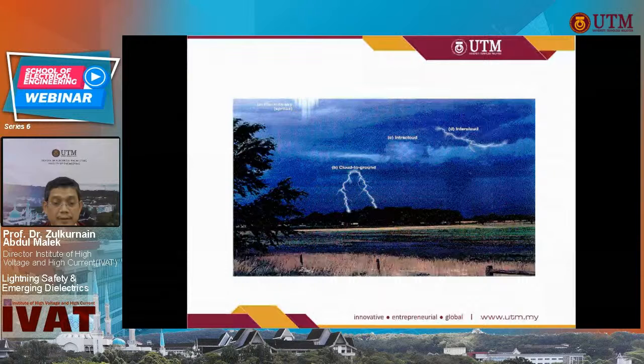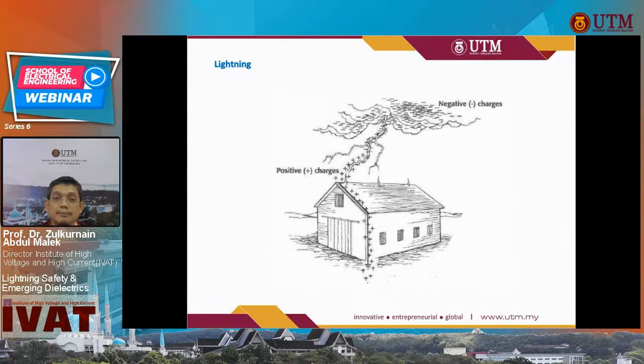So when the leader is connected from the ground object, a very large current will flow, as you can see here. Basically, the positive charge will flow upward to discharge the negative cloud. And doing this will cause a very large current to flow, up to 200 kA maximum. And this large current will cause a very high voltage at the point of entrance in the ground. And this will cause a very high touch and step potential, which is dangerous.